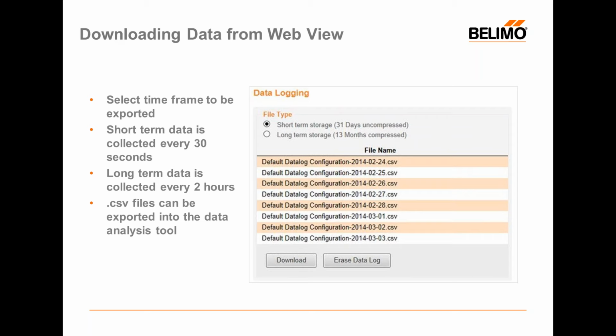I mentioned a little bit earlier when we spoke about the data log chart and historic trends that we do store trend information in the energy valve. And as we can see here, we have two different file types. We have a short-term range file that is a 31-day uncompressed file that's going to take a sampling of the objects every 30 seconds. And then we have a longer-term storage, which is up to 13 months. And that's going to take snapshots of the objects every 2 hours or less.